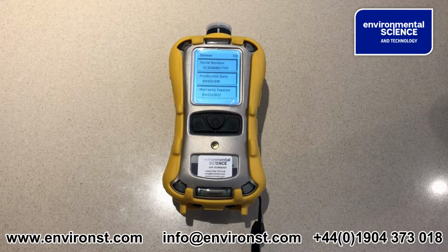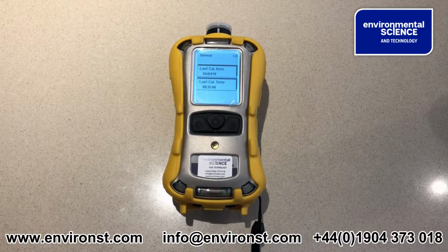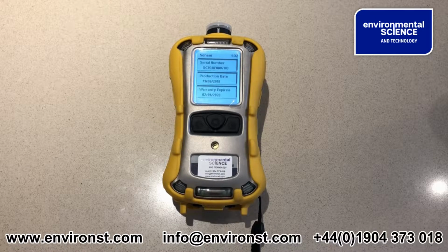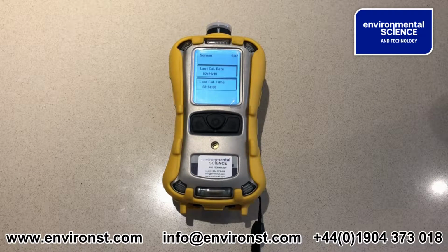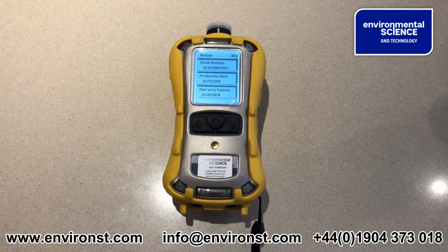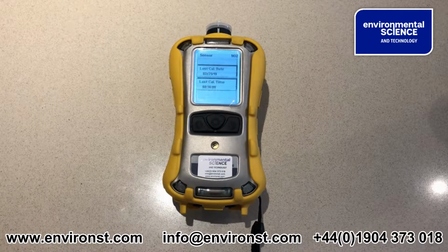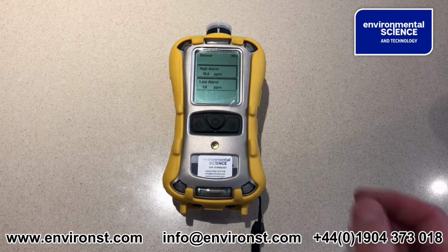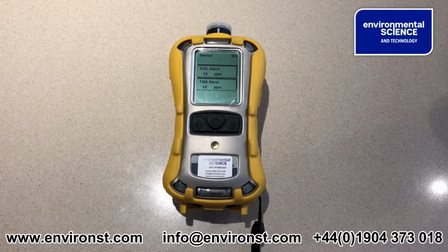What it's doing now is going through all of this information, but this is also allowing the unit to warm up and the sensors to stabilize before you actually use it. There is a reason for this almost delay tactic. For all gas monitors, you should allow them to start up and warm up for a duration before you even think about using them, because chemical reactions in the electrochemical sensors take a while to stabilize. So let's just leave it to warm up. We'll probably fast forward through this.